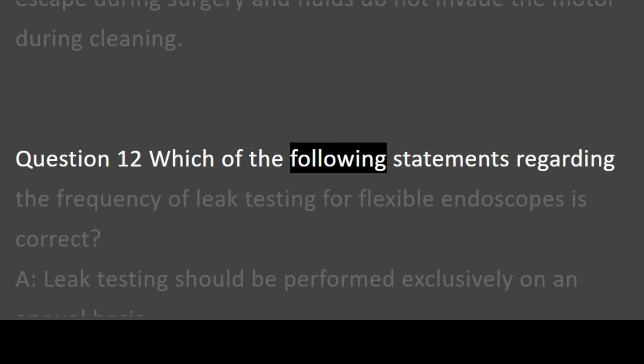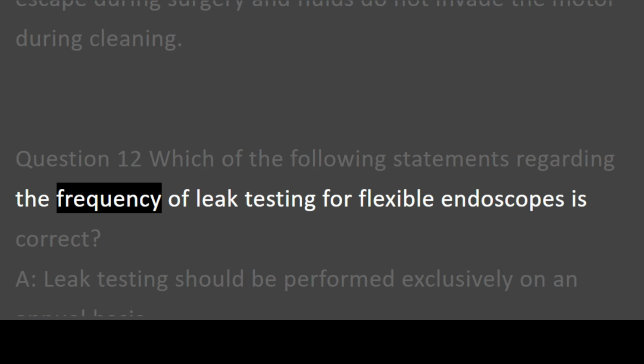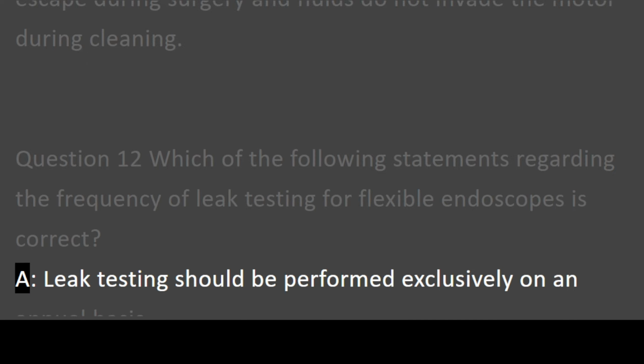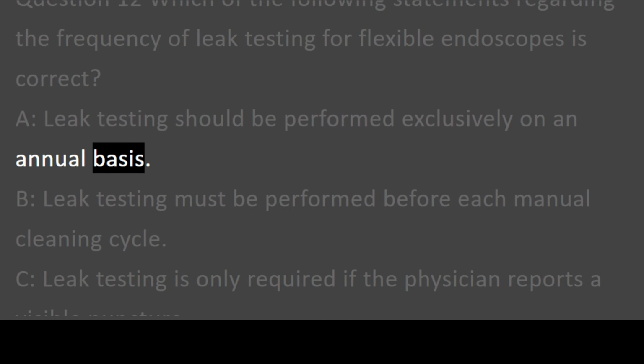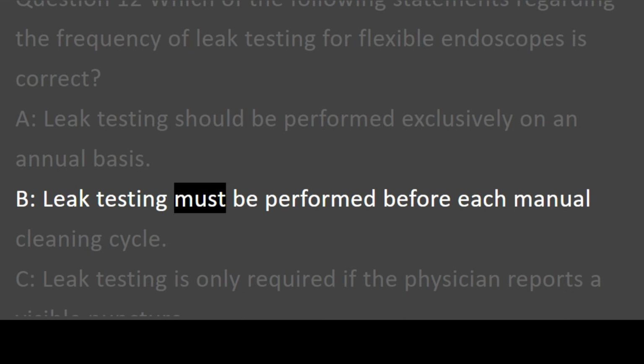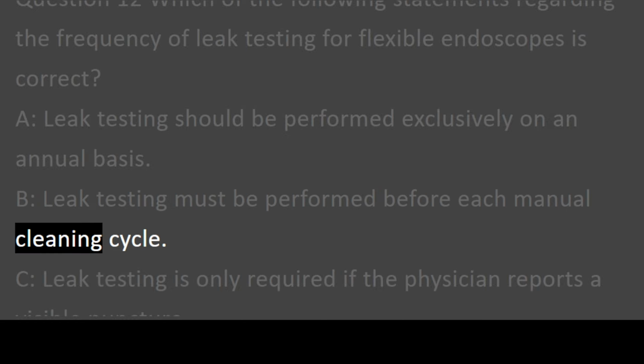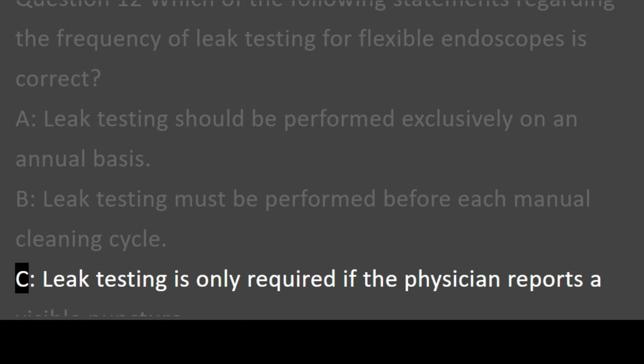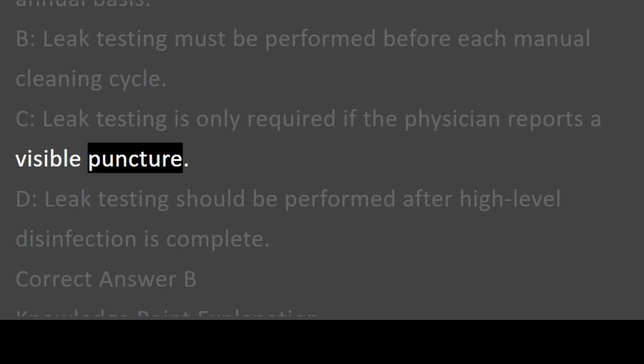Question 12. Which of the following statements regarding the frequency of leak testing for flexible endoscopes is correct? A. Leak testing should be performed exclusively on an annual basis. B. Leak testing must be performed before each manual cleaning cycle. C. Leak testing is only required if the physician reports a visible puncture.